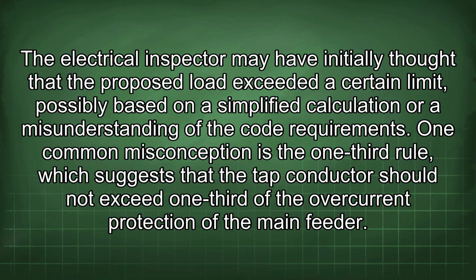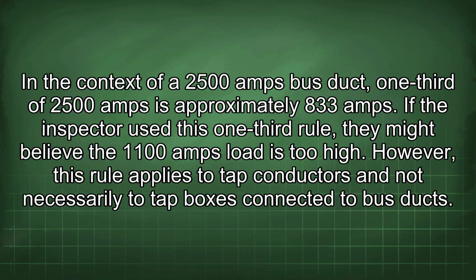One common misconception is the one-third rule, which suggests that the tap conductor should not exceed one-third of the overcurrent protection of the main feeder. In the context of a 2500 amps bus duct, one-third of 2500 amps is approximately 833 amps. If the inspector used this one-third rule, they might believe the 1100 amps load is too high. However, this rule applies to tap conductors and not necessarily to tap boxes connected to bus ducts.